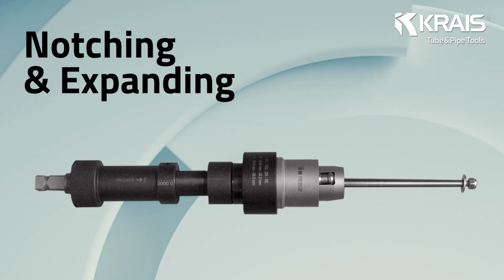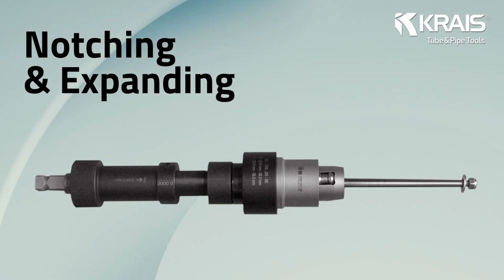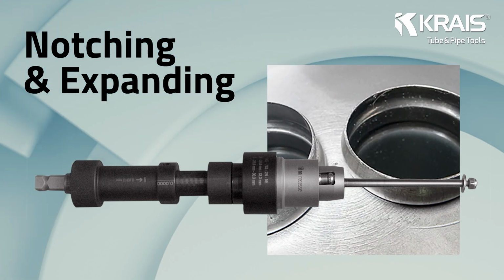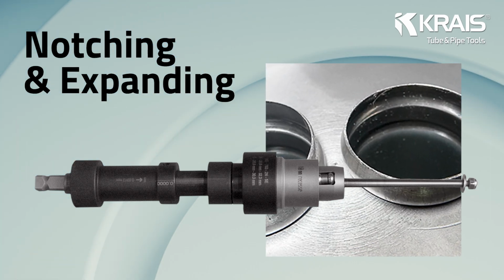KRAIS NE notching and expanding combines expansion with notching or mechanical locking features to retain the tube on both sides of a thin tube sheet. It is selected where tube loosening is a known risk in thin sheet constructions, always aligned with the equipment specification and acceptance criteria.